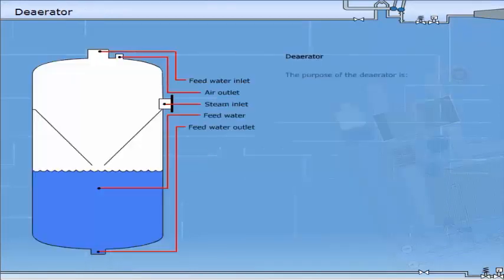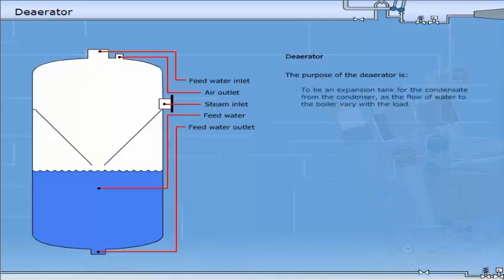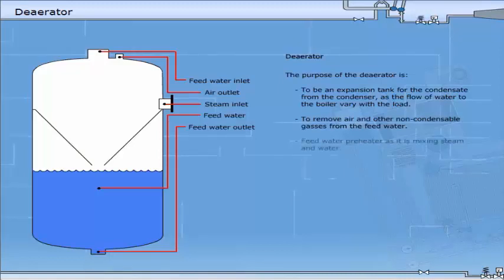The purpose of the de-aerator is to be an expansion tank for the condensate from the condenser as the flow of water to the boiler varies with the load, to remove air and other non-condensable gases from the feed water, to preheat the feed water as it is mixing steam and water, and it may be a condenser for several minor steam consumers.